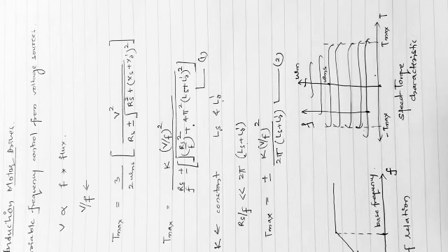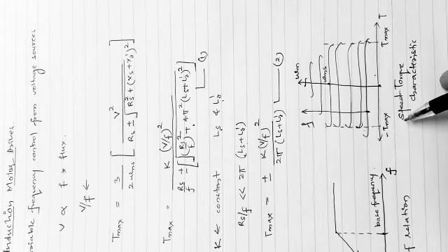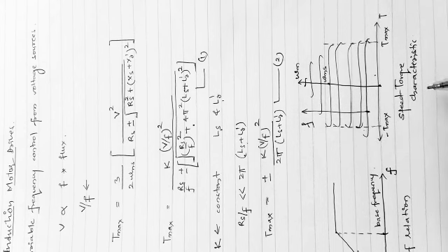We can note some features of variable frequency control. First, we can control the speed and braking operation from zero speed to above the base speed. Second, during the transients, that is during starting, braking, or speed reversal, the operation can be carried out at maximum torque. Next, copper losses are low, hence efficiency and power factor are high, as the operation is restricted between the synchronous speed and the maximum torque point at all frequencies. Finally, the drop in speed from no load to full load is very small.